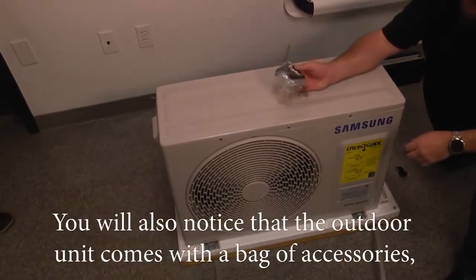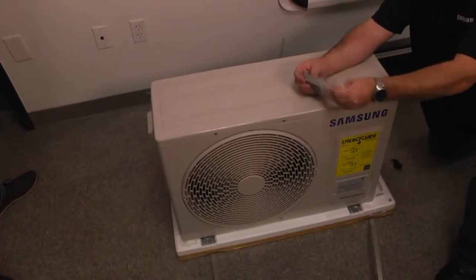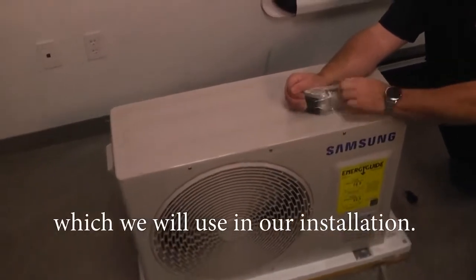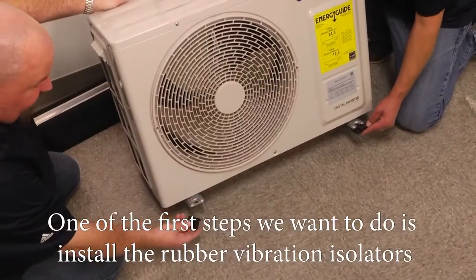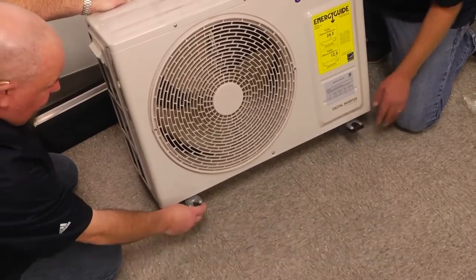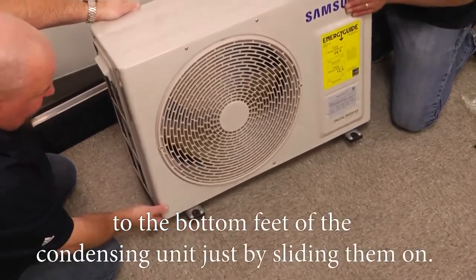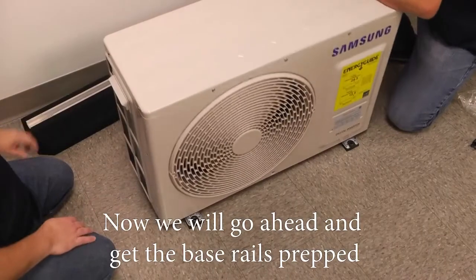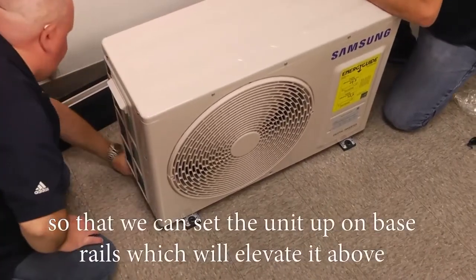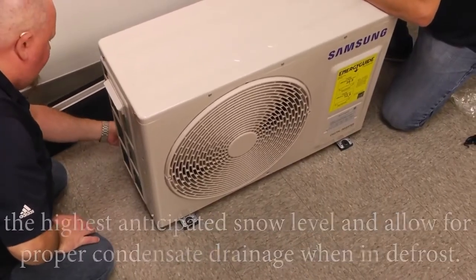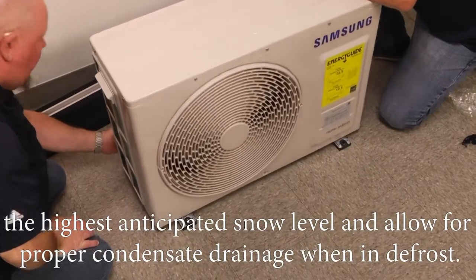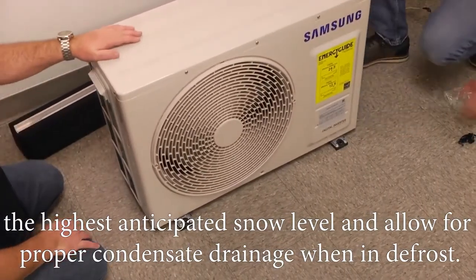We'll also notice that the outdoor unit comes with a bag of accessories, which we will use in our installation. One of the first steps we want to do is install the rubber vibration isolators to the bottom feet of the condensing unit just by sliding them on. Now we'll go ahead and get the base rails prepped so that we can set the unit up on base rails, which will elevate it above the highest anticipated snow level and allow for proper condensate drainage when in defrost.